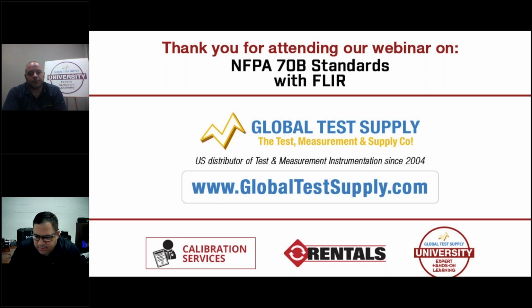UL certification always comes up with this. So our devices, or the components themselves, the IR windows, are UL certified as appropriate for use in those applications. What the organization will need to do, and this is typically our recommendation - there's a couple things I want to call out specifically. On our round IR windows, our mounting process does allow for a screw-back type installation, so there are no additional penetrations beside the punch out - that's a unique component to our IR window. And two, what we recommend is when an organization is looking to install a series of IR windows, they can get their cabinets recertified. So you need to contact UL and have a representative come out to recertify all of the cabinets. But we've never had an issue with an organization that's done that getting them recertified as safe.